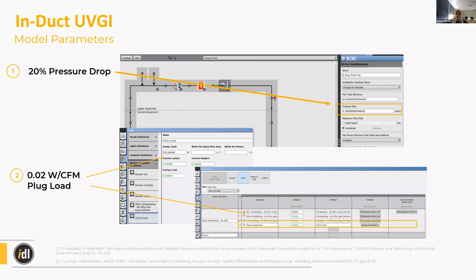So if you remember back to one of the first slides I showed you with all of the site EUIs for the different technologies, in-duct UVGI actually had a negative site EUI, which meant that we have a potential for energy savings. That's something we had read about, but all the research was done in Florida and I think Singapore as well, really humid climates. So we were really curious to see how this would pan out for Boise, where it's very dry and we're a heating dominant climate, but it did show that there is potential for energy savings. That is because the UV lights are disinfecting the cooling coils and decreasing the pressure drop across the coils. So just like the MERVs, the fans don't have to work as hard to push all that air through. With this one, we actually modeled a 20% drop in pressure, where the MERV and the HEPA were a rise. So that is what accounts for the energy savings.